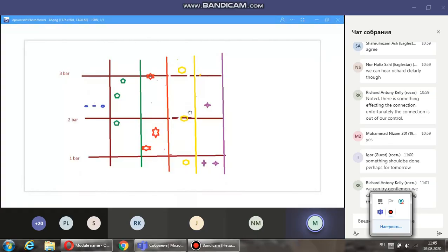So the logic is, if you invalidate any one of them, the remaining two, whatever the value there, they will take the average, no matter if it is more than 1 bar also. That is the logic there. So this can happen when the sensors are faulty.